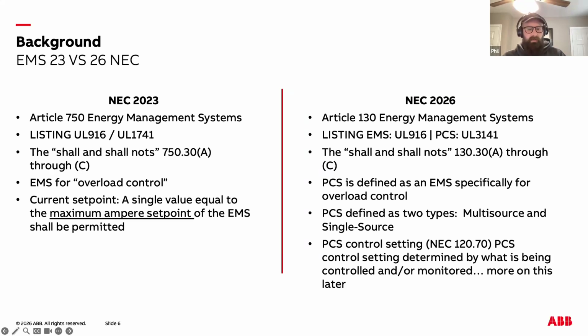So the 2026 NEC reorganizes these systems into Article 130 and draws a sharp formal distinction between EMS and PCS. This is one of the most significant conceptual changes in the code cycle. The move from Article 750 in the 23 NEC to Article 130 in the 26 is not just cosmetic. It's a signal that energy management is becoming a foundational part of electrical system design.